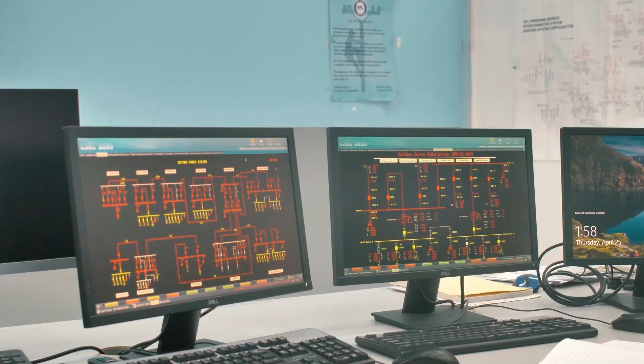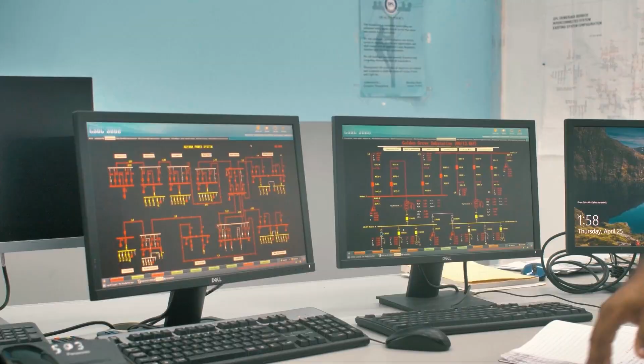It is low right now, and it's telling us that the demand is greater than our available generation. So in order to balance the demand and the capacity we have, we just opened a feeder to maintain the 60 hertz which we have to operate at. Now any deviation from that 60 hertz means there's an issue in the grid. If it's too high, we have too much generation. If it's too low, then we have an excess of demand.